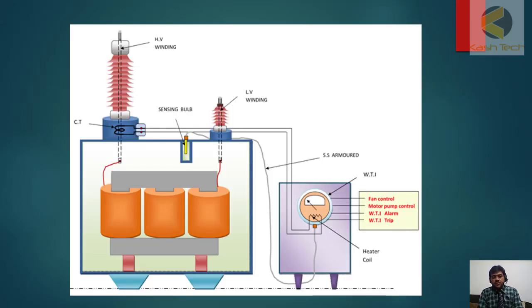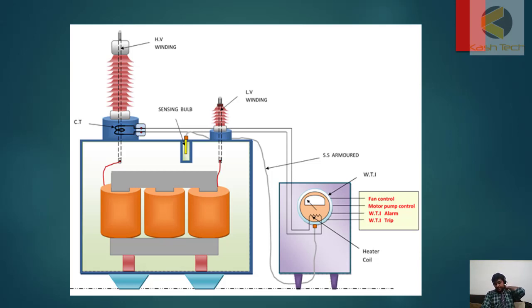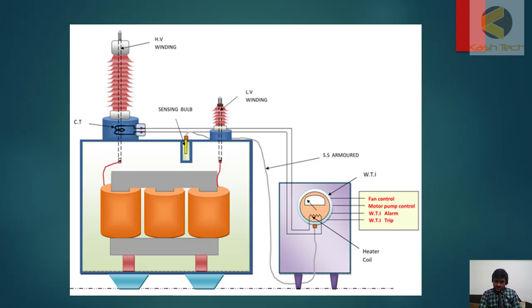There are two types of indicators: oil and winding. For the oil temperature indicator, the sensor is dipped directly in the oil so you can measure the oil temperature. However, the winding temperature indicator does not measure the real winding temperature of the transformer.